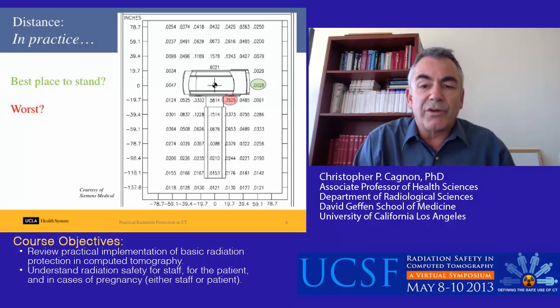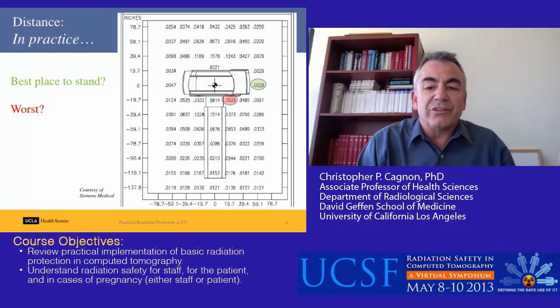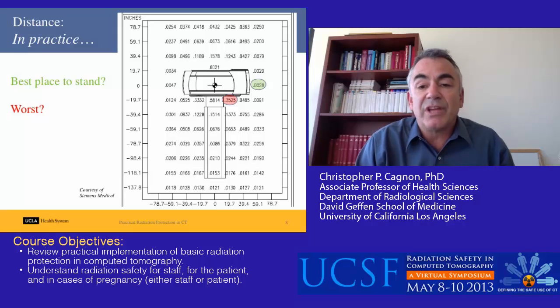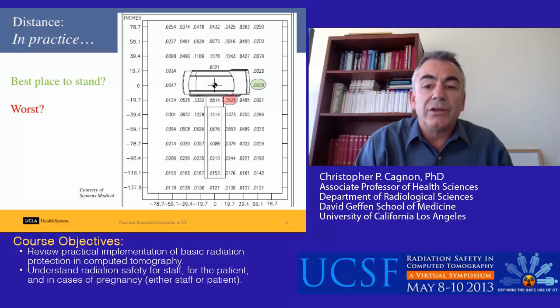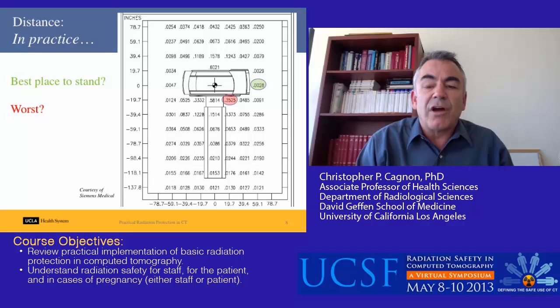The absolute worst place to stand is right in the corner between the gantry and the table, which is of course where the individual generally stands to insert and guide the needle or any other device. The absolute best place to stand — and this is all unshielded, just in the scan room with the patient — is directly off to the side of the gantry, where the gantry itself provides the most protection, a small fraction of the exposure at the gantry-table junction marked in red.